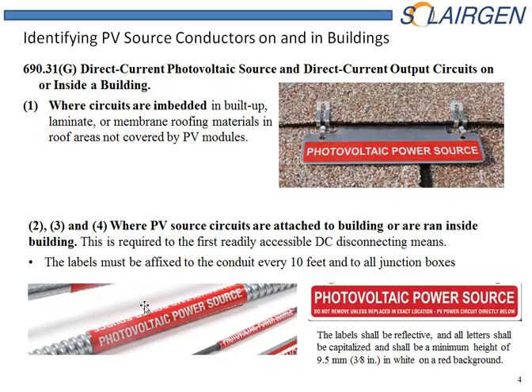Anytime you run a source circuit on a building or inside a building, up until you reach the first readily accessible disconnect, you must label it with photovoltaic power source. If you embed these cables into the roof rafters and this part is not underneath the PV array, then you actually have to go on the roof and identify this circuit, so that if first responders showed up to cut holes, they wouldn't be cutting through a DC circuit.